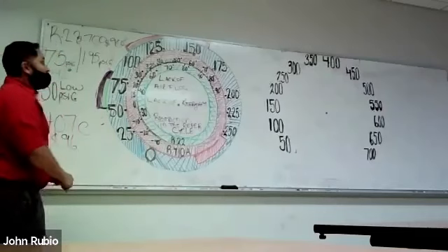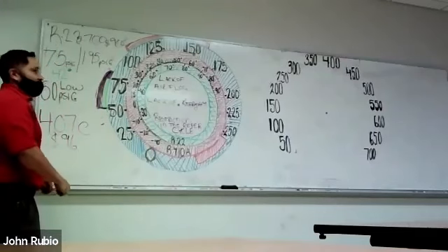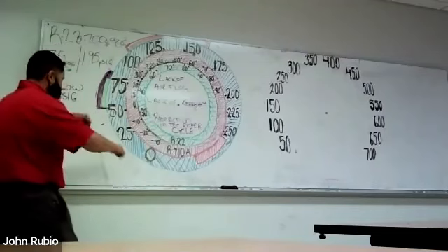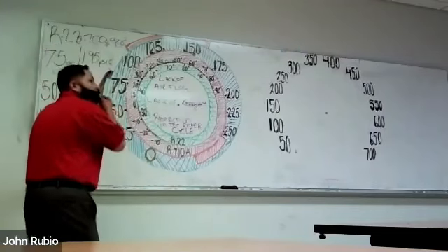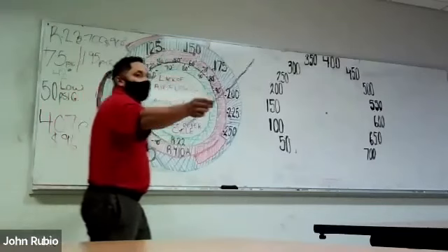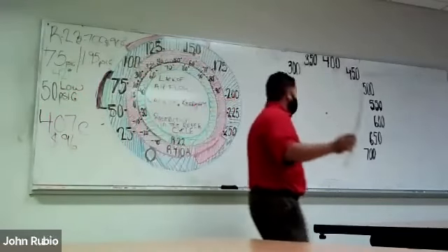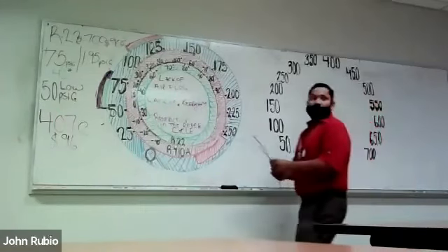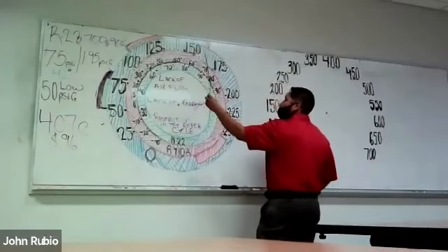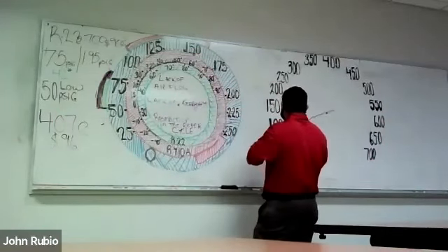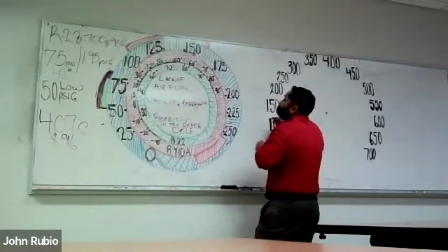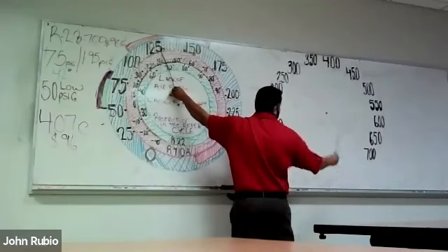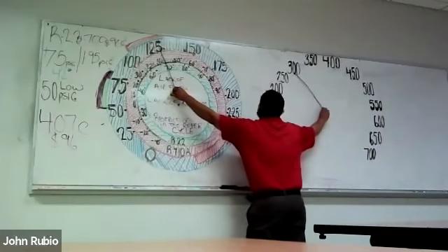Many technicians never use the high side. How will they ever catch a restriction? They won't. This is how we tell. If we look back at yesterday's notes, where we have the typical operating pressures, we remember that we had, following my needles, we're going to run 410A. Typical running pressure is 125 over typically 300.